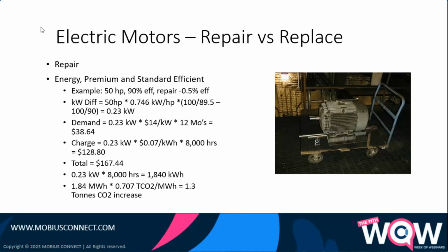So if we do that, that's 0.23 kilowatts. And then we run through the same formulas, and we come up with a $167 increase in energy cost after a repair, and 1.3 tons of CO2 increase per year. So when I take a look at it, all of our decisions directly affect energy and emissions.